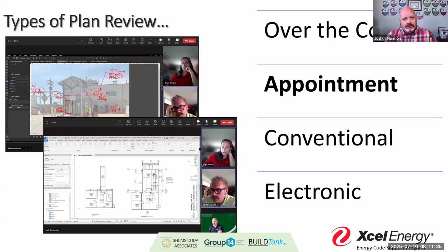The conversation I'm having with the design firm on a particular project right now is, I'm confused. We've talked about heating load calculations. We've talked about wall designs. They're not the same. Bring them together. Let's look at them side by side and we'll confirm if we're designing a building based off of this, then I need the details to match so that when it's built, it matches what you design the equipment to be based upon, right?